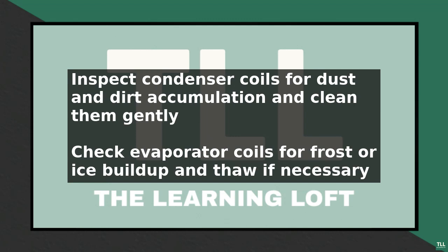Inspect the condenser coils, located at the back of the unit, for dust and dirt accumulation. Use a soft brush or vacuum cleaner to gently clean the coils, taking care not to damage the fins. Also, check the evaporator coils, located inside the unit, for frost or ice buildup. If you find any, turn off the unit and let it thaw before restarting.